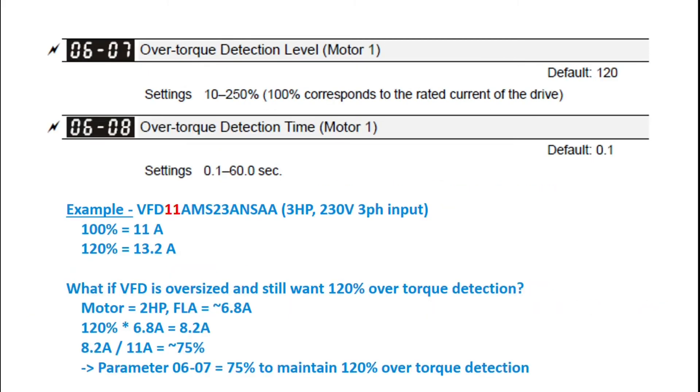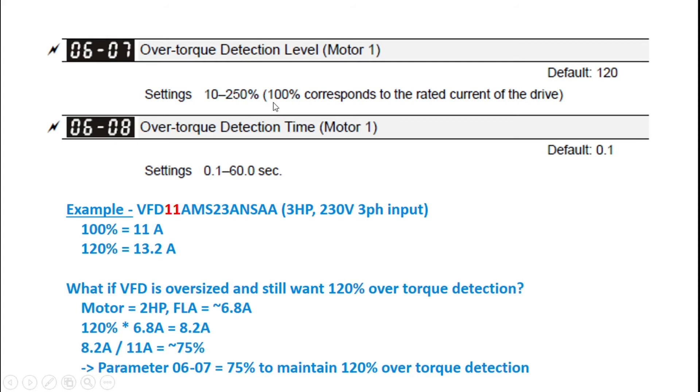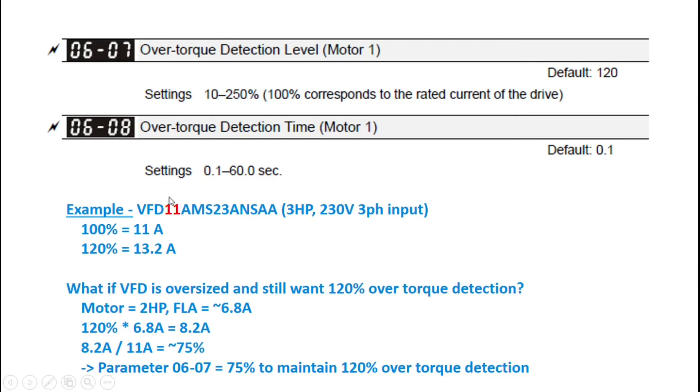The other parameters for over torque detection, 0607 is your over torque detection level. So it's a percentage. The default is 120%, where 100% corresponds to the rated current of the drive. So if you're using, for example, this MS300 model, this number I've got highlighted in red is your rated current of the drive. So for this model, 100% would be 11 amps, 120% would be 13.2 amps.